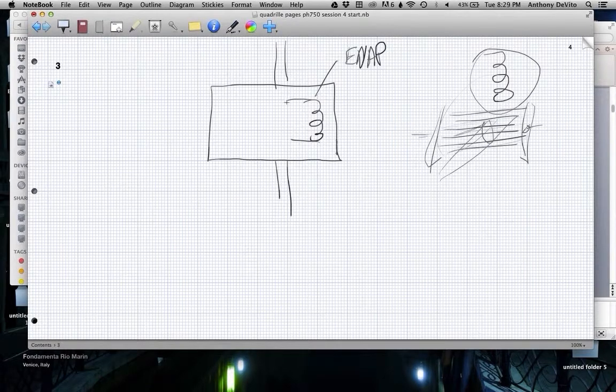To get back to this, this is called an evaporative coil. It's called an evaporative coil because what you do with this coil is you send liquid Freon into it. You release it through a little metering device. There's a capillary tube, or it's called an expansion valve, right? A lot of times it's not even an expansion valve. Sometimes it's just a very thin tube that allows liquid Freon to flow into this coil.